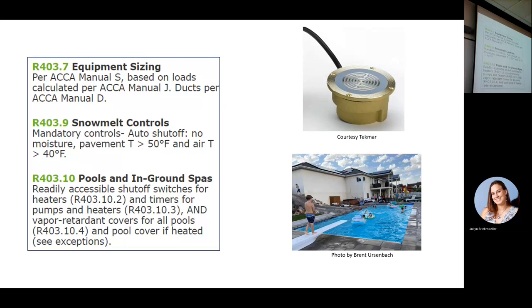For 2 or 3 code cycles now, we already talked about that. If you use a snow melt system, you have to put a sensor in it now. For a lot of years, we didn't have that in the code, and people would say, well, I got a timer, or I got a switch, and if it's going to snow that night, I watch the weather, I turn it on, and then it doesn't snow, and the driveway gets warm, and it just keeps getting warmer and warmer and warmer, and it's really wasteful when we get in that type of situation.